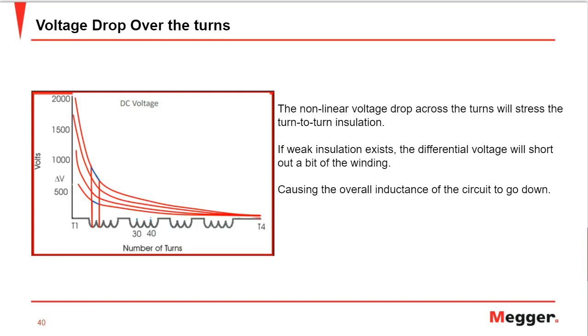So that's why, as mentioned previously, surge testing replicates those real lifetime situations while doing the testing. And when we apply higher voltage with the rise time differences, we can expose these weaknesses as we get the graph of the results, and we can determine the insulation condition depending on the waveform shifting to the left. And let's talk in more detail about why the rise time is an important factor for doing surge testing.